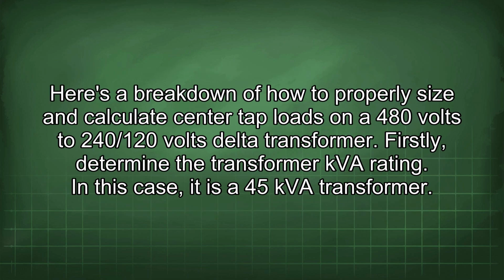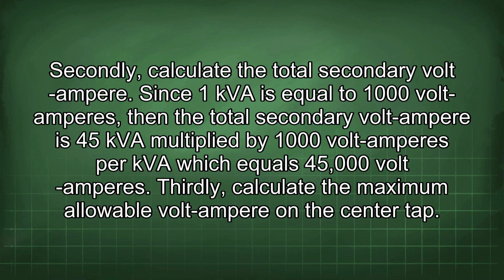Here's a breakdown of how to properly size and calculate center tap loads on a 480 volts to 240/120 volts delta transformer. Firstly, determine the transformer kVA rating. In this case, it is a 45 kVA transformer. Secondly, calculate the total secondary volt-ampere. Since 1 kVA is equal to 1000 volt-amperes, then the total secondary volt-ampere is 45 kVA multiplied by 1000 volt-amperes per kVA, which equals 45,000 volt-amperes.